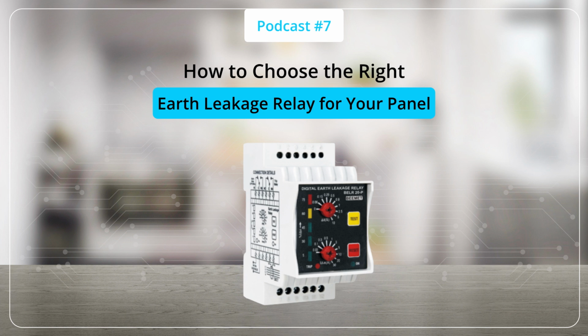Every safe and functioning electrical panel requires protection against leakage current. Electrical panels play a vital role in daily operations across commercial, industrial, and residential environments. However, undetected leakage currents can become a hidden threat that compromises both equipment reliability and personnel safety. Even small amounts of electrical leakage can increase the risk of electric shock, fire, and equipment damage. This is where earth leakage protection becomes an essential safety layer for electrically powered systems. An earth leakage relay, commonly known as an ELR, responds quickly to leakage faults, helping protect people, equipment, and property while supporting compliance with electrical safety requirements. Because of this, ELRs have become an important component in modern electrical panels.